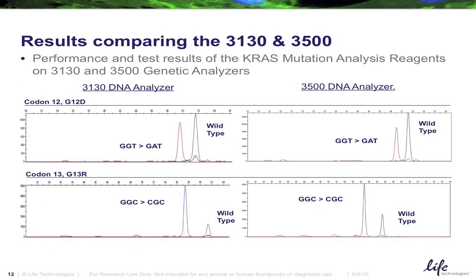Here is an example of what the data looked like. We see a very clear mutation peak in relationship to a very clear wild type peak. In terms of these two instruments, the data is very similar with just a very slight normalization of the background on the 3500.